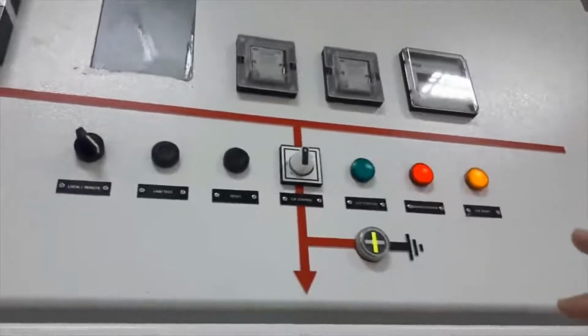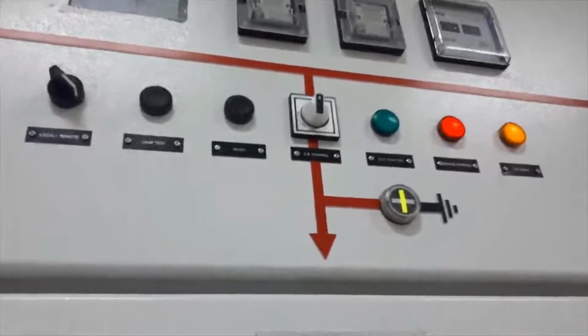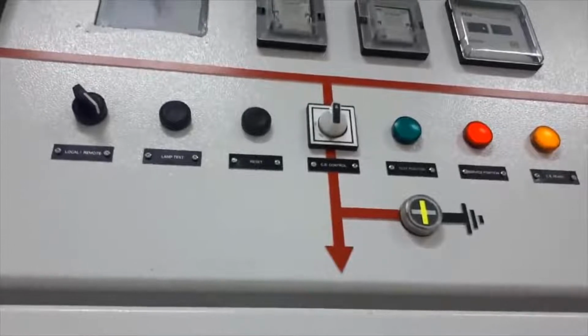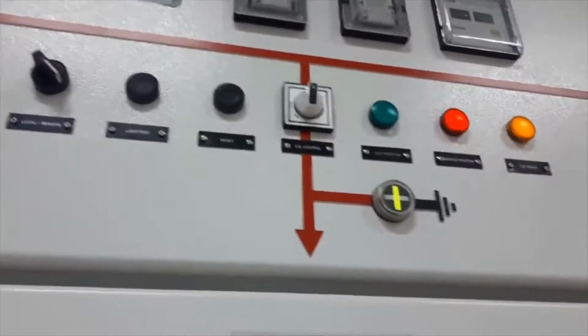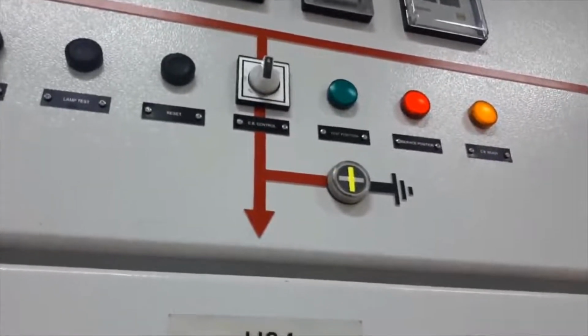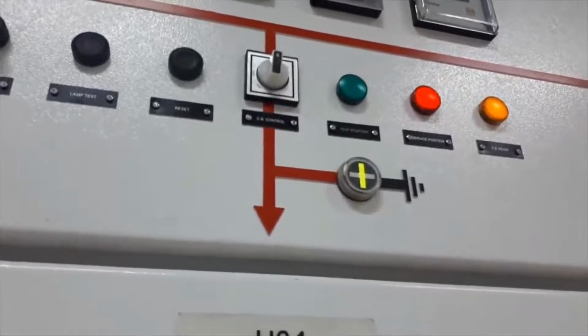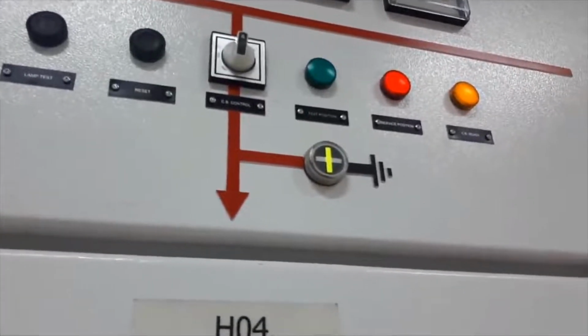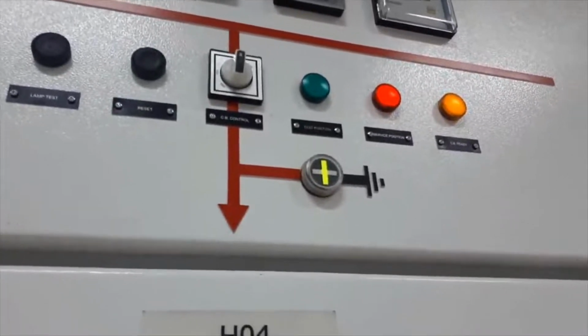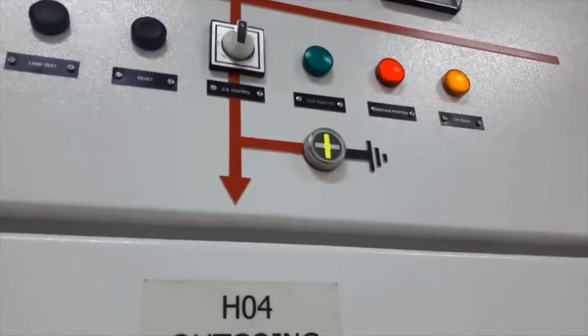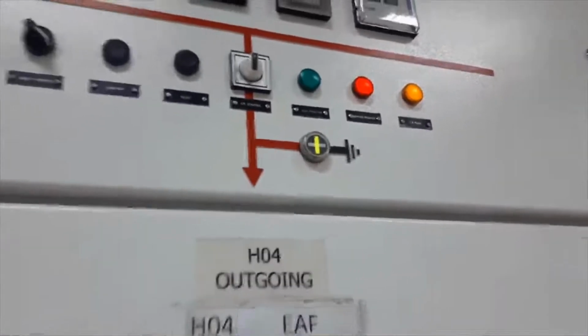We have the lamp test, which if we press, the lamps will light up. We have a reset knob that resets the lights. If the breaker is in test position, this light will be turned on. In service mode, this red light is turned on, which is also on now. CB ready will be turned on when the breaker is ready to close, which is also on at the moment.